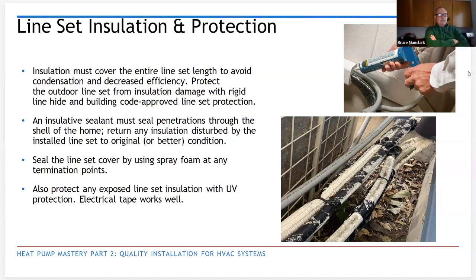Yeah. Here's another really good question. I like this because I was confused about this for a while. Should both refrigerant lines be insulated? I see a lot of only one pipe covered instead of both for the outdoor lines. Good question, Matthew. So I use the word unitary, that's what I call a conventional heat pump. With those systems, you have a metering device inside and you have a metering device outside. When the metering device is on the inside, that's where you'll see the one line insulated and the other line not insulated. When we switch over to mini splits, like the photo here, those metering devices are only in the outdoor unit. There's no metering device at the indoor unit. In that instance, you're going to have both lines insulated.